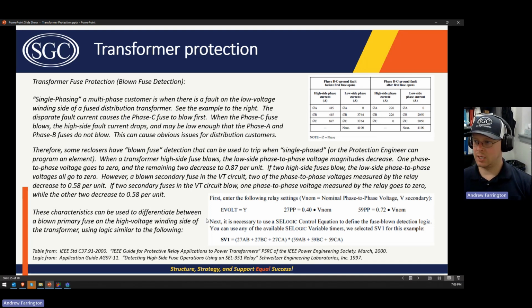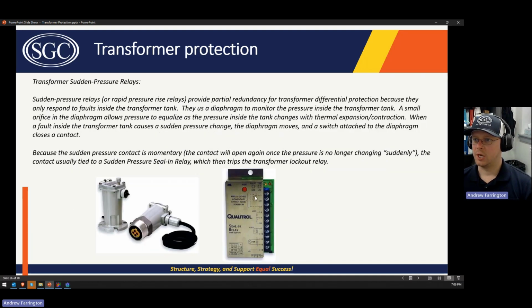So there's a way to mitigate against that, called blown fuse detection, and it has the ability to differentiate between the voltages that you would see on the low side of the transformer if a high side fuse is blown versus if a fuse in the VT secondary is blown. Those voltages look different, and there's an SEL guideline on how to do that. So I mostly just know that exists.